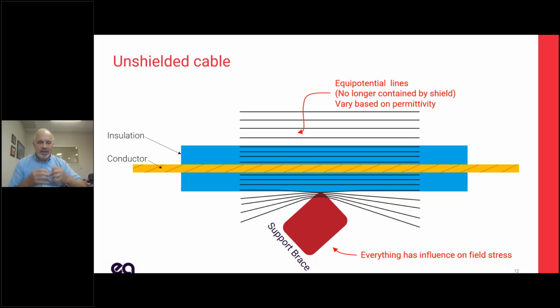If we didn't have a shield on our cable, we would have a situation like this, where these equipotential lines, which represent the electric field, are not constrained within the insulation. They go on forever, effectively, until they hit a conductor. In this picture here, I've got the support brace. This support brace has a different permittivity from the insulation. The air has a different permittivity from the insulation. So what happens when you have a different permittivity is you get a concentration of electric field, a variation in the electric field, instead of this nice even distribution that we have in the shielded cable.